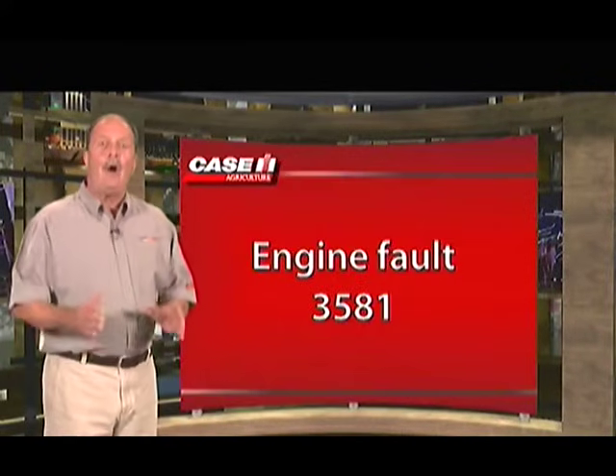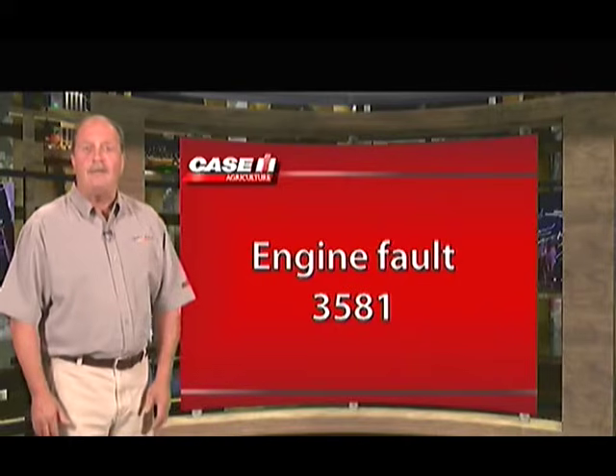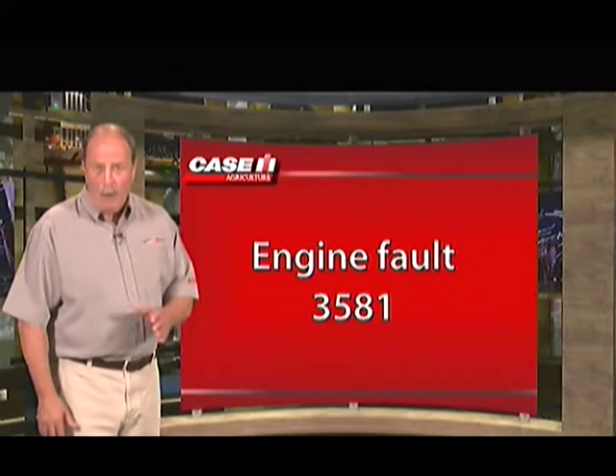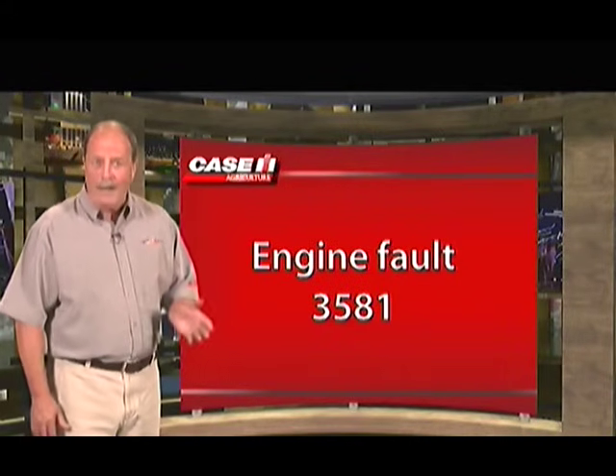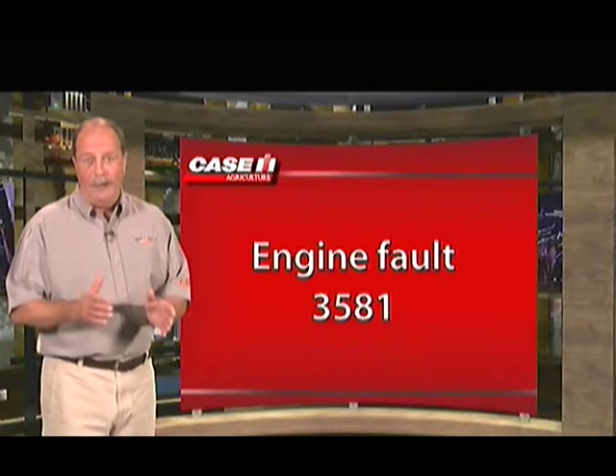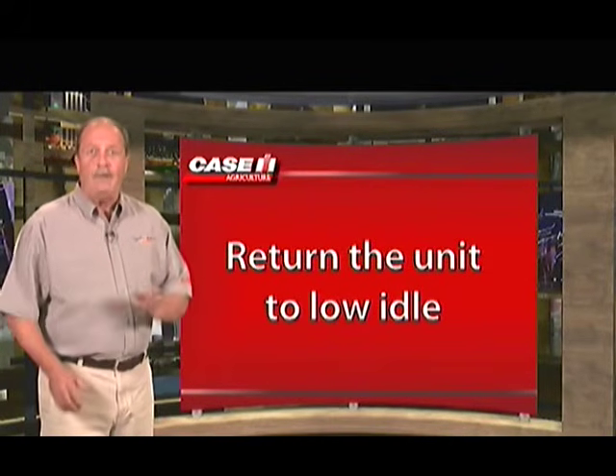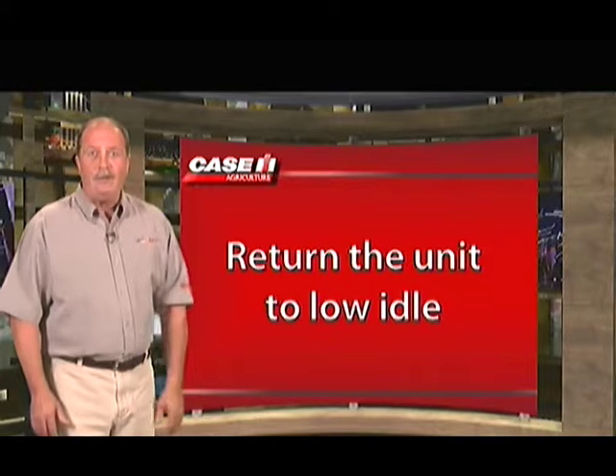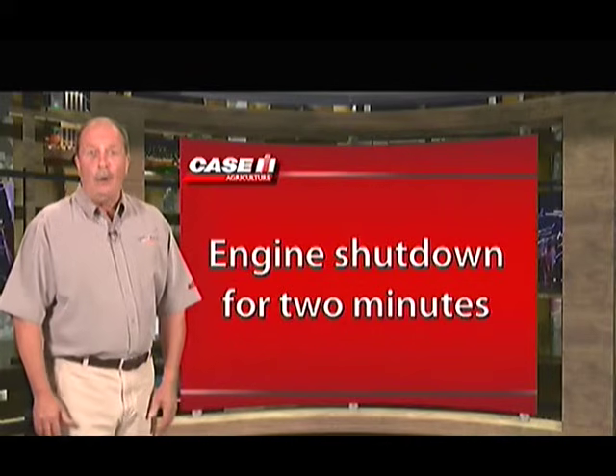You may hear an audible sound when the emissions test message disappears, along with the engine fault 3581 still appearing on the display. If this occurs, return the unit to low idle. The engine fault display should be cleared and the unit will return to normal operation. You can also clear the fault with an engine shutdown for 2 minutes.